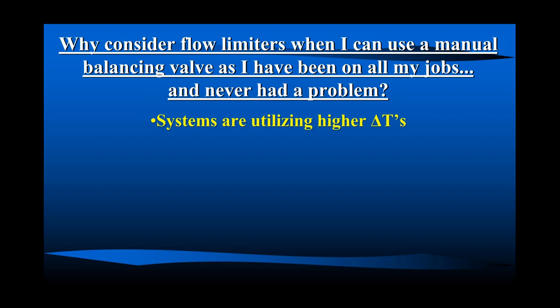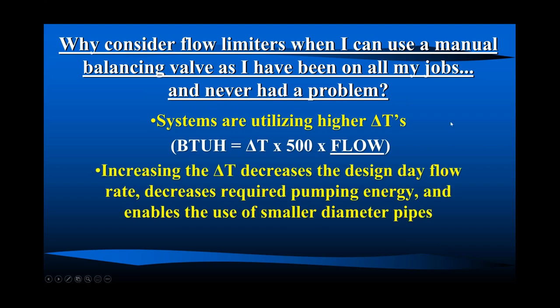So we're going to design systems utilizing higher delta T's, right? Basic equation equating load to flow: BTUs per hour equals delta T times 500 times flow. That's a constant times flow. Load is load, right? We're in the comfort business as well. We're not going to change that. But we can change delta T, and that directly affects flow. Higher the delta T, flow goes down. And if we do that, our pumps get smaller, therefore their motors get smaller. And maybe we can decrease the size of the pipe involved.